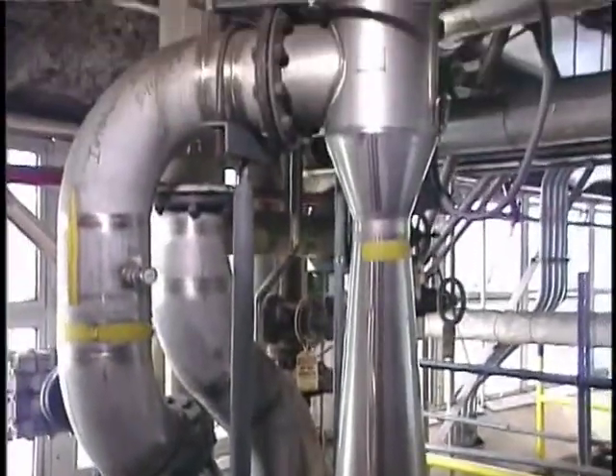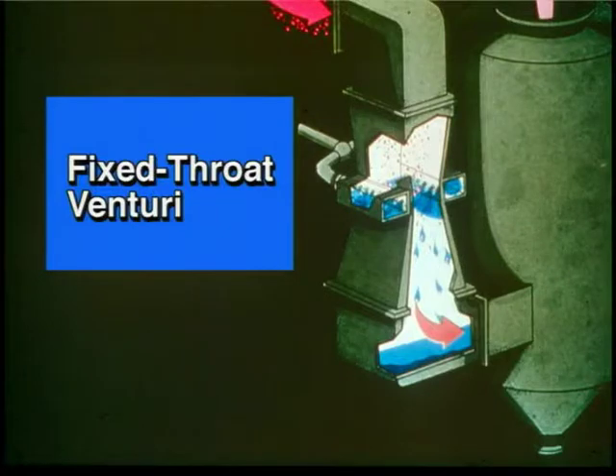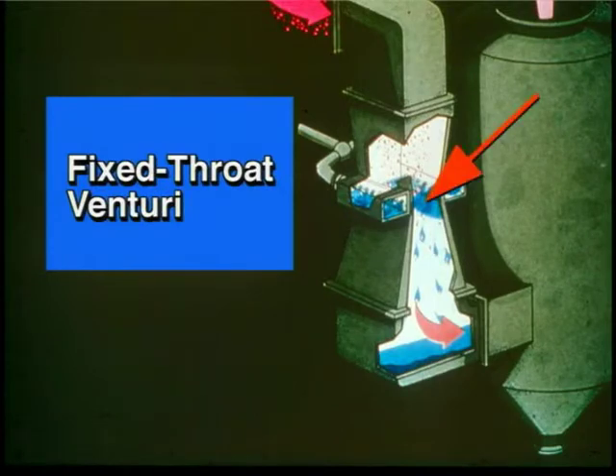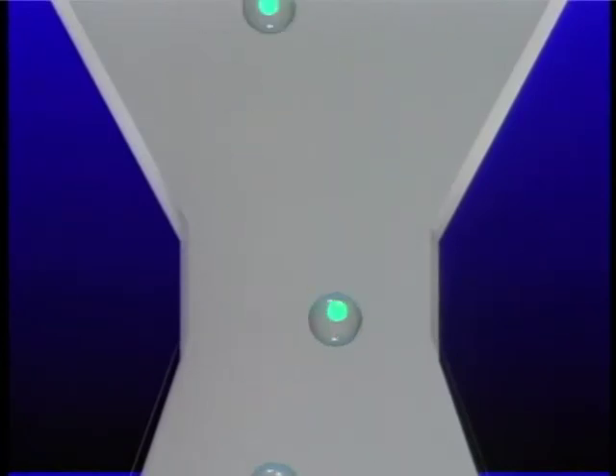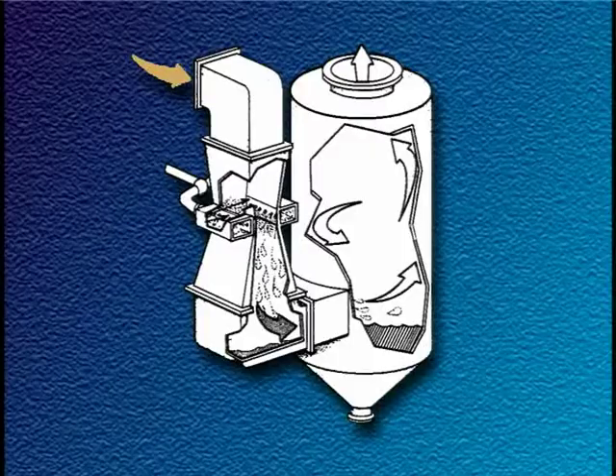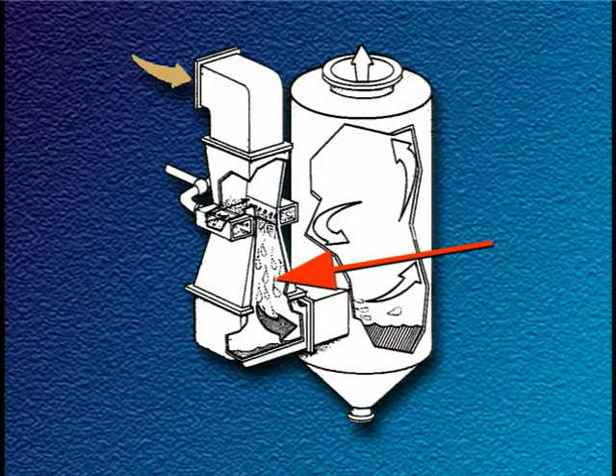The most common high energy wet scrubber is the venturi, although it can be operated as a medium energy scrubber. In the fixed throat venturi, the gas stream enters a converging section where it is accelerated toward the throat section. In the throat section, the high velocity gas stream strikes liquid streams that are injected at right angles to the gas flow, shattering the liquid into small drops. The particles are collected when they impact the slower moving drops. Following the throat section, the gas stream passes through a diverging section that reduces the velocity. Some particle collection also occurs in this section.